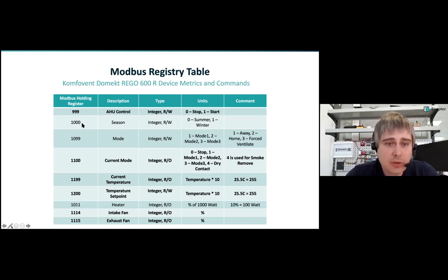So let's have a look at the register number 999. This register is responsible for starting and stopping the ventilation unit. So if we write 0 into this register over the Modbus, the unit will stop. If we write 1, the air ventilation unit will start.